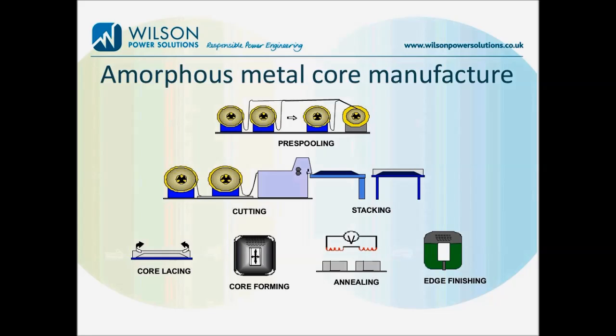So let's now look at the process for amorphous core manufacture. Compared to conventional CRGO core manufacture, it's really very much different. Now, amorphous metal is an alloy in the form of ribbon, so it's a tenth of the thickness of a standard core steel at 0.025 mm. There are only 3 standard widths available from Hitachi Metals in the USA, and the width of material selected depends, of course, upon the design of the transformer.